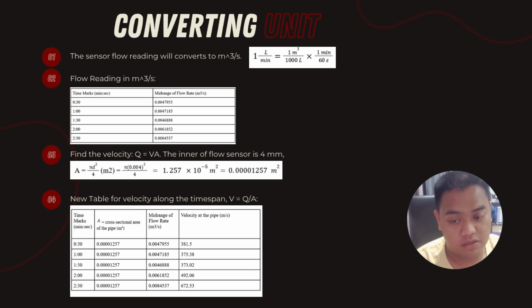From then on, we'll find the area of the flow meter, which from our finding of the spec of the flow sensor will be 4 millimeter. So it will be pi times 0.004 to the power of 2 over 4. So we get our area of the inlet of the flow sensor will be 0.00001257 meter square. With that, we shall be dividing Q, which is our volume flow rate, by area. We shall be finding the velocity in meter per second.